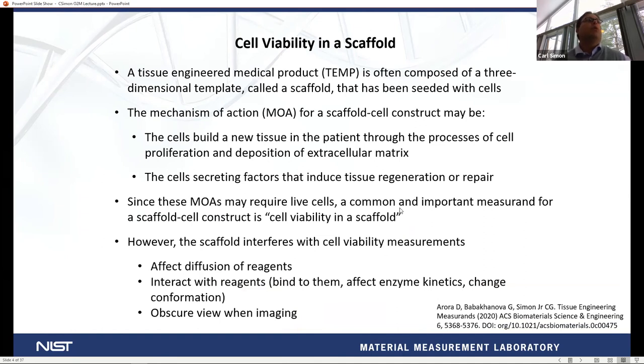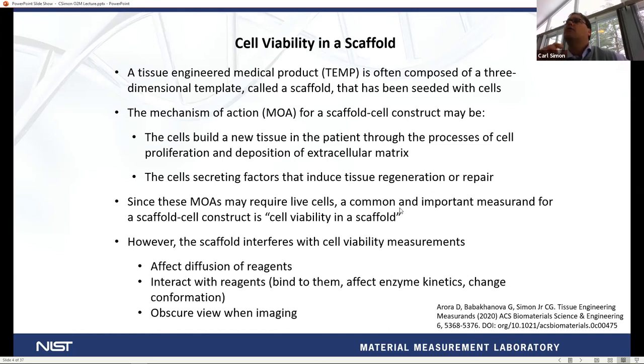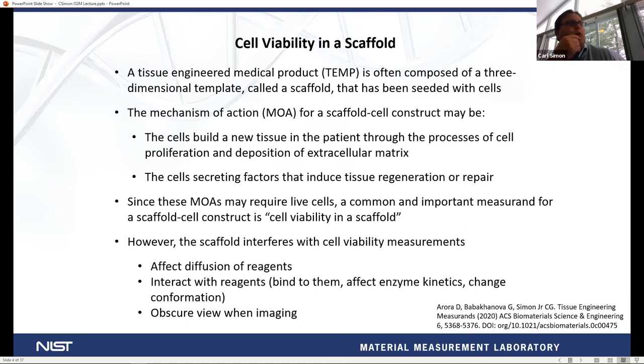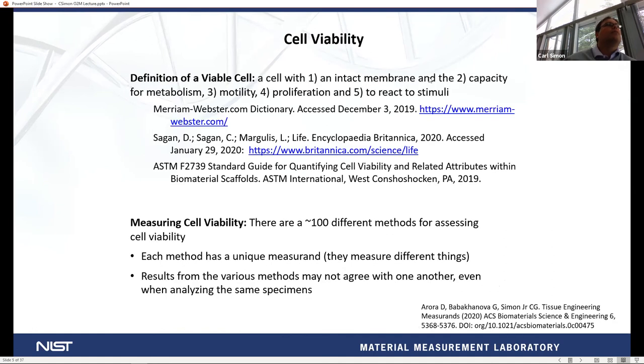Cell viability in the scaffold — why is it important for tissue-engineered medical products? Because they're often composed of a scaffold, a three-dimensional template seeded with cells, and the mechanism of action is that the cells would build new tissue, either through proliferation and deposition of matrix or secreting factors to recruit other cells. These mechanisms require live cells, which is why cell viability is a common and important measure. The problem is that the scaffold interferes with many measurements — it affects diffusion of reagents, can interact with reagents by binding or affecting enzyme kinetics, and if you're imaging, it can obscure imaging.